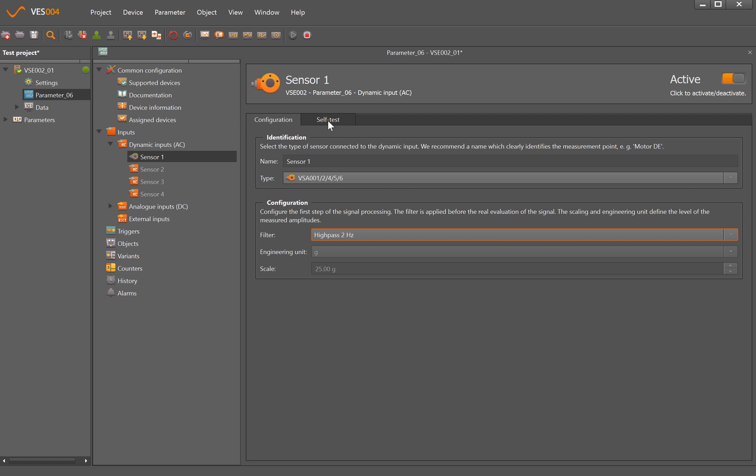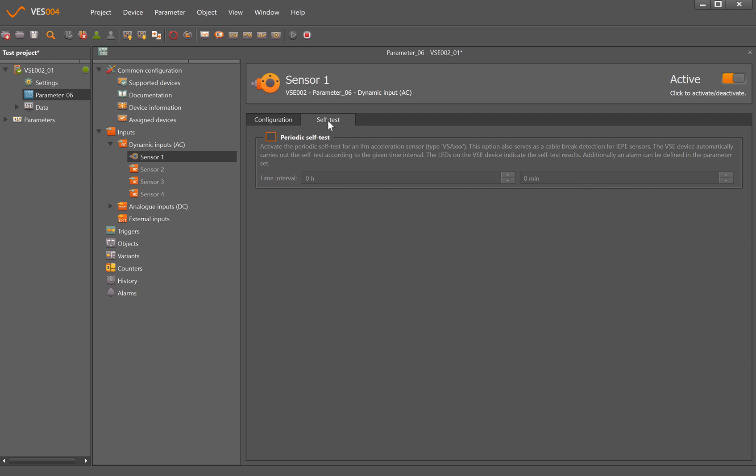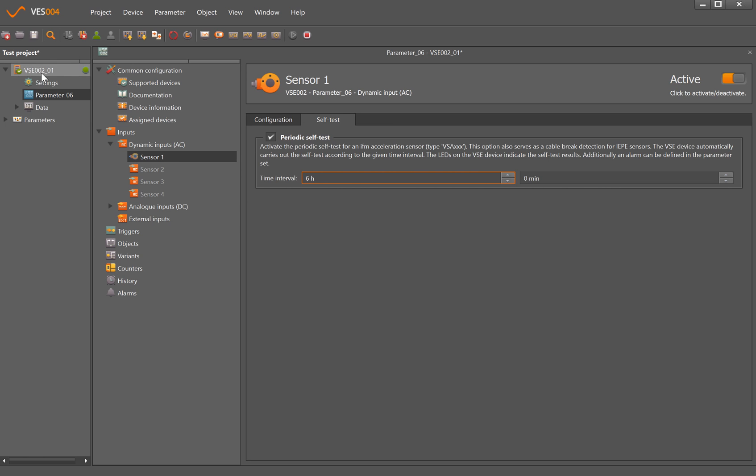The other option you have here is self-test. So if I was to tick this box and change that to say every six hours, the VSE002 module will perform a self-test of the MEMS accelerometer to make sure it's still within spec. If it detected a problem or the wire was broken or the sensor had been damaged, the VSE module would then alarm to the control system to confirm that the sensors are no longer working correctly.